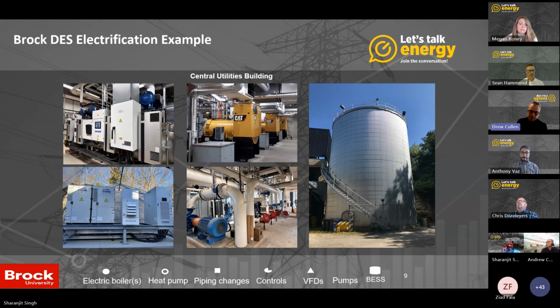We use the cogen plant to power all our critical buildings on campus by islanding the plant. Some of the equipment in these critical buildings doesn't like a change in power or delay in power during an outage, so we island the plant to avoid that kind of disruption. That's where the battery energy storage system, or BESS, came into play. To run 1 engine, we had to provide 2.5 megawatts of electricity, which is the electrical demand for the critical buildings. You can't do that with 1 engine.